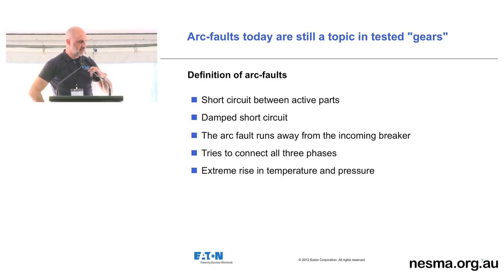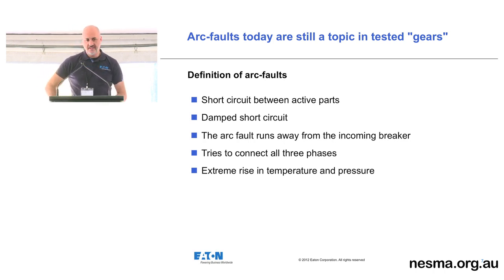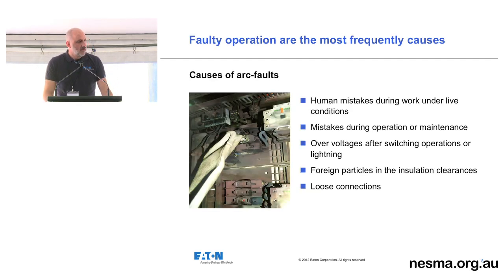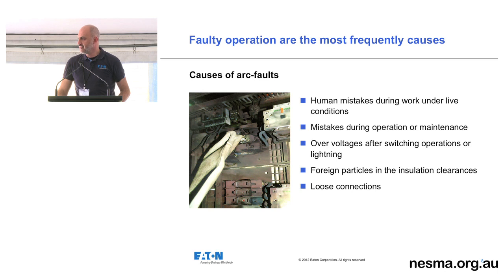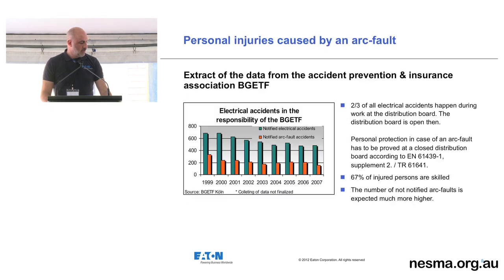An arc generally runs away from the incoming breaker, tries to connect all three phases. The major impact of all that, of course, is the extreme rise in temperature and pressure. There's statistics about the heat, that it's many times, like a multiple factor of the surface area of the sun. It's that severe. As we know, accidents do happen in our industry, so even those who've got the tightest of regulations on working on boards, whether they're live or dead, accidents do happen. There's a graph there. Disregarding where that graph came from, no matter what statistic you look at on the internet, there's always an incident rate of accidents that happen in our industry.